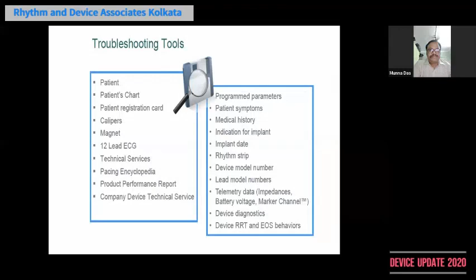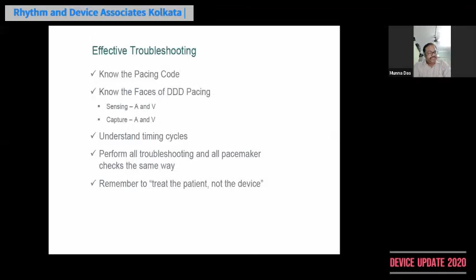Next slide. So the troubleshooting tools include the patient first, the calipers, magnet, a 12-lead ECG, technical services, help from our industry people, as also the pacing encyclopedia, the product performance report, and we need to know when the implant occurred, what the device model was, the telemetry data, the device diagnostics, and the whole entire lot of information before coming to a particular conclusion. Next slide. So for effective troubleshooting, we should know the pacing code, know the faces of DDD pacing, sensing, that is the atrial sensing, the ventricular sensing, the atrial capture, ventricular capture, understand the timing cycles, and perform all pacemaker checks the same way. This is very important. And remember to treat the patient, not the device.